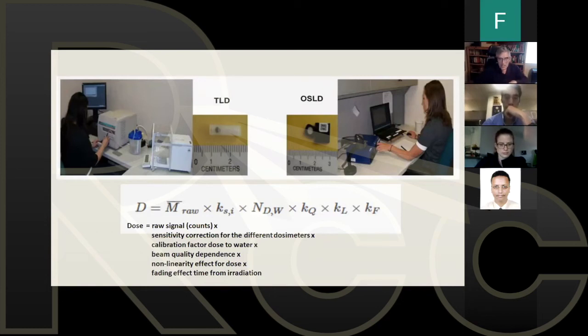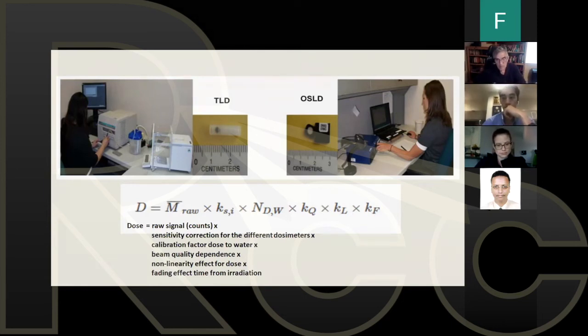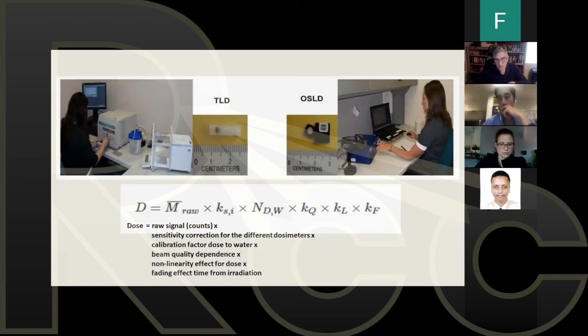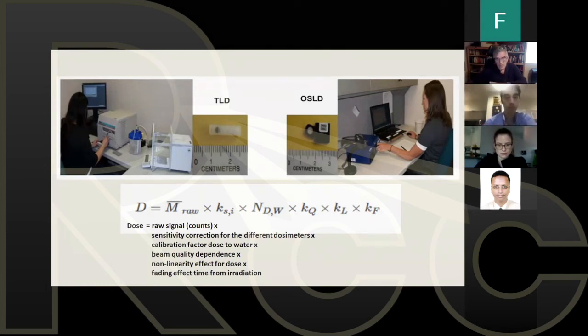but the air ionization chambers, I have personally not witnessed a change in sensitivity. I would be very concerned if a chamber came back with a significantly different calibration factor. And by that, I mean probably 1%. If a chamber came back 1% different from what it was 2 years ago, I need to think that maybe something changed in that chamber. Maybe I banged it. Maybe somehow some water got inside of it. Maybe when I was unscrewing the protective cap, I may have loosened the connection a little bit. So they will change if mechanically you've done something to change them. But if they're carefully taken care of and intercompared regularly, you won't see a change.